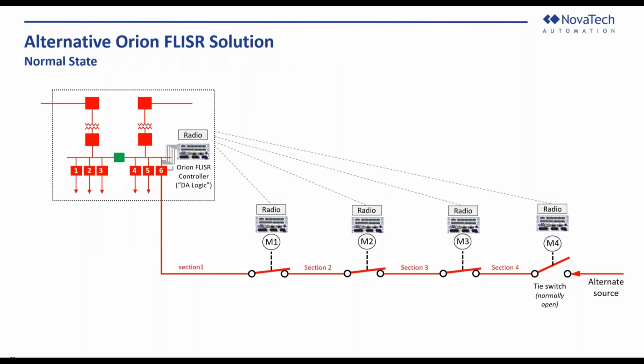So now we're going to take a look at an example of a fault on a distribution line, and how a FLISR controller would isolate the fault and sectionalize it. Here we have a similar concept. We have the FLISR controller at the sub, and it's constantly talking over radio to M1, M2, M3, M4, and similarly they have an alternate source that's coming in, where the tie switch is normally open. It's able to monitor the overcurrent faults, report demand amps, and also monitor and control each individual switch. So what happens if a fault occurs somewhere in this line?